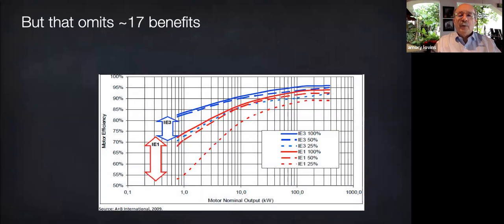Now here's a graph showing the same issue over about a 500-fold range of motor size on the horizontal axis on a log scale. As standard efficiency induction motors in red go from 100% to 50% to 25% of their rated load, that is from solid to dashed to dotted, their efficiency falls off down the vertical axis more or less steeply, especially at the smaller sizes. This is for IE3 in blue, or the old standard IE1 lousy motors in red. So they have a lower efficiency. The IE3s don't fall off as much at part load. That is, the more efficient models have flatter efficiency versus load curves, which is a valuable attribute.